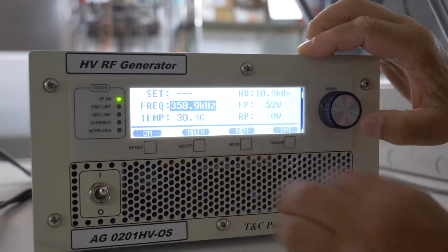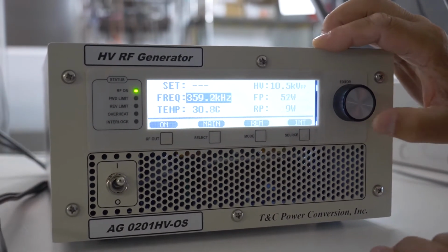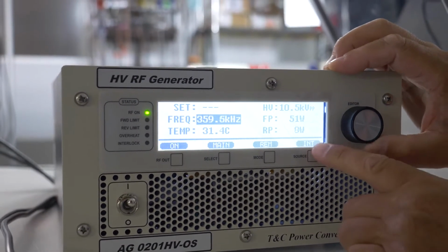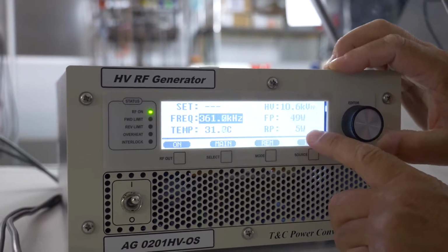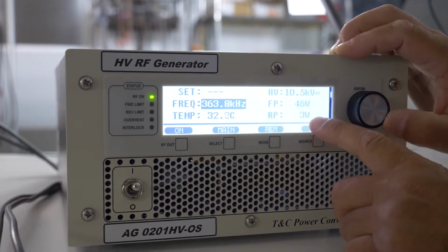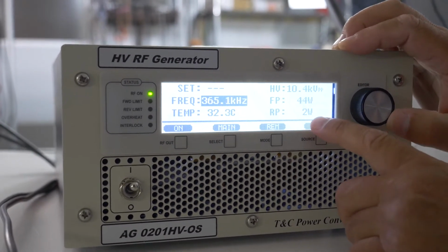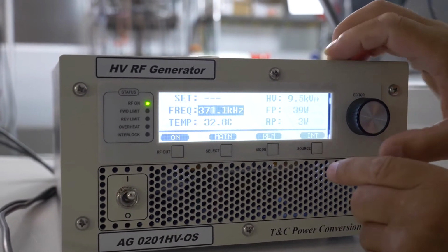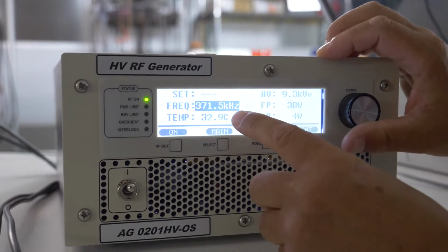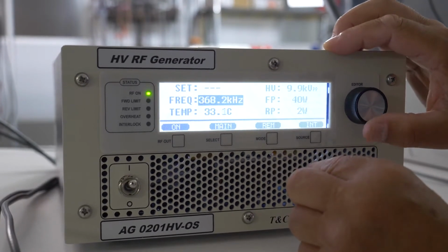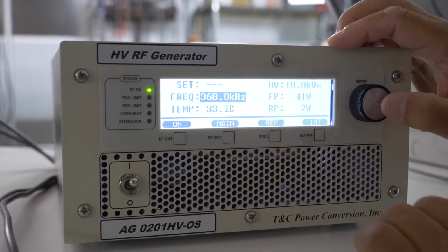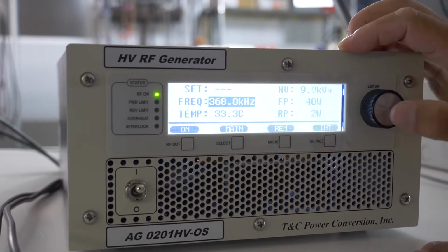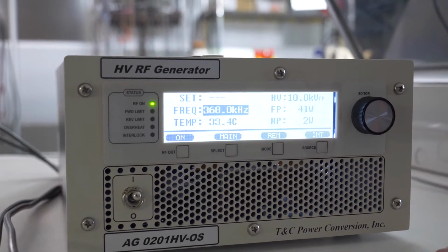For that purpose, by trying, we have to use the editor left, right, and see which direction will offer us the lower reflected power, and we continue until we find the minimum of reflection. Minimum close to zero. Okay, I pushed too much, so I have to go back with the setup, and at this point I decided that my best point is 368 kilohertz of operation, and leave it there.